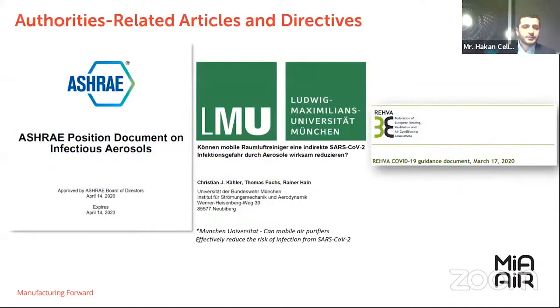There are some declarations which have been published by these authorities. According to them, the way to avoid the contagion is air purifiers. For example, as per ASHRAE, if the existing air treatment system is not able to operate with 100% fresh air, it's a must to use air purifiers in the indoor area to reduce the risk of contamination. As per the same declaration, the filtration efficiency class of the air purifiers has to be HEPA class filters or high MERV classes, they are saying.